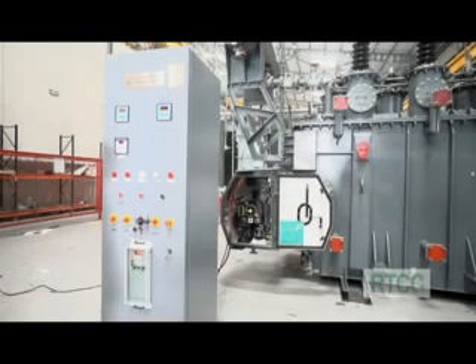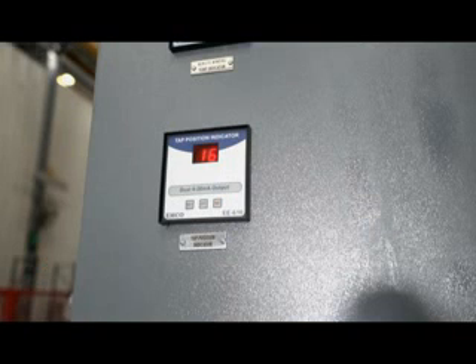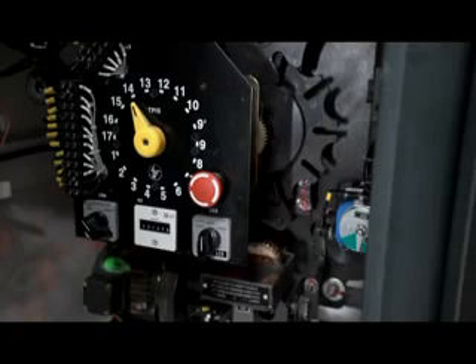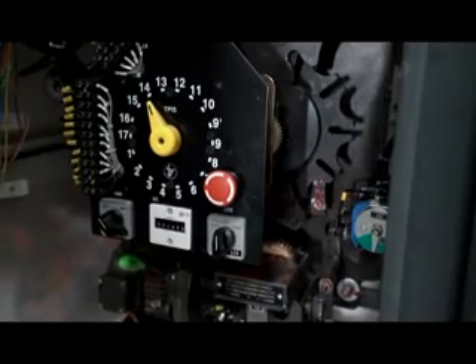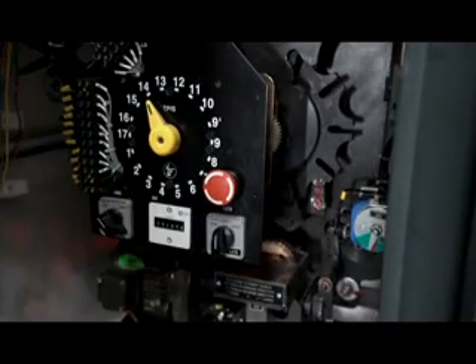Remote Tap Changer Control Cubicle (RTCC) is an indoor panel whose main objective is to control the transformer's tap changer from remote. This panel houses, among others, an AVR, automatic voltage regulator, which can be utilized to regulate transformer voltage using principles such as the master follower method or circulating current method. Approved numerical protection relays, selected for the best quality and latest technology in its design.